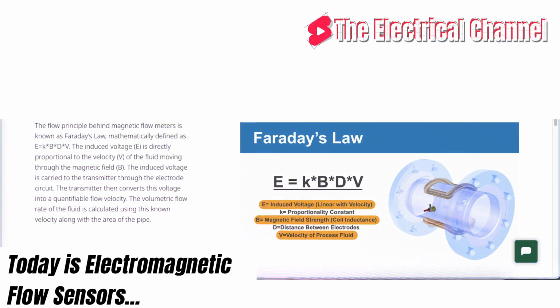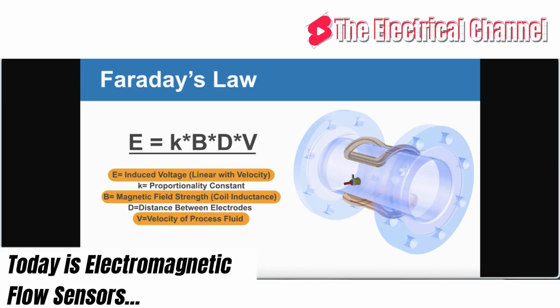Magmeters can be used to measure all electrically conductive liquids, with or without solids. Examples: water, wastewater, sludge, slurries, pastes, acids, alkalis, juices, and fruit mashes. The rule of thumb for magmeters is anything that can be pumped can also be measured. A highly valued trait in measurement technology. Typical tasks include measuring and monitoring continuous flow rates, filling and dosing, as well as applications in custody transfer.